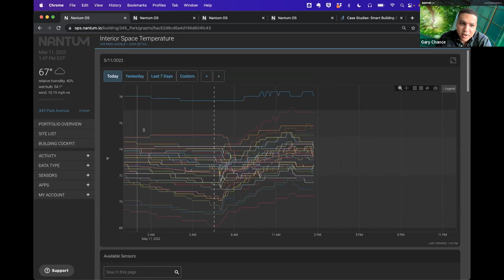What you'll also see here are these gray boxes. As the BMS starts up, as an example, this is the time the BMS started up this morning, you'll see temperatures start to reach their SLA requirements. This light gray box here is the best SLA requirement zone, so you can quickly visualize which of your sensors are meeting the SLA requirements. These lighter gray zones still meet the requirements, but it's a quick way for an operator to visualize, for example, a specific sensor in a specific zone that might be misbehaving, to go identify what's happening. The general idea is to understand building performance in real time.